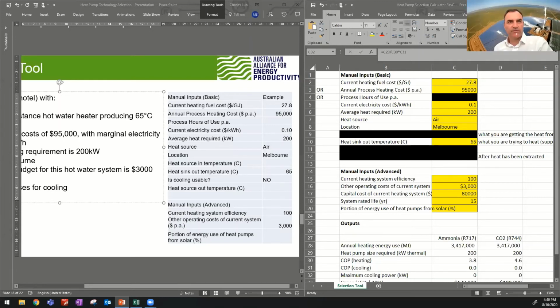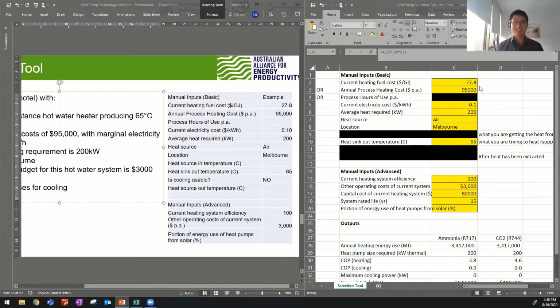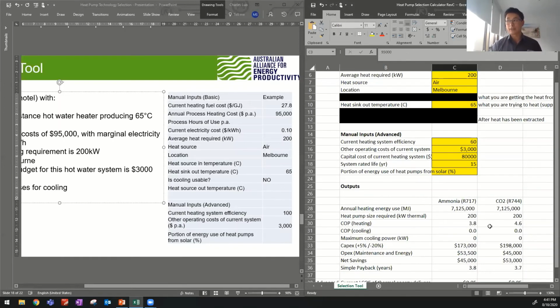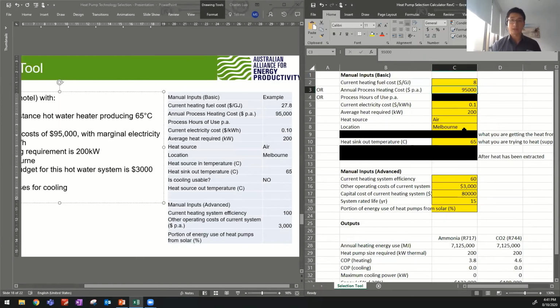We've got a question about regional areas where heat pumps would often displace LPG. I think we've covered that when we talked about the cost per gigajoule, around 27.8, which sounds about right for volumes for LPG. So it's just a matter of making those adjustments, as Charles mentioned before. You can do not just LPG boilers, but any sort of boiler, including biomass boilers, just by changing the efficiency.